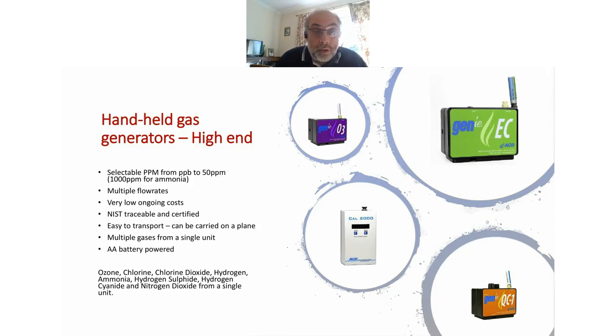Each gas is, of course, an additional cost. In addition, some of these are ATEX approved, some are not. So there's always a discussion about which is the best. It doesn't affect the cost of the instrument. It just affects which instrument you might choose for other reasons. Powered simply by AA, or in some cases AAA batteries, and can produce a range of gases at this ppm or even ppb level.